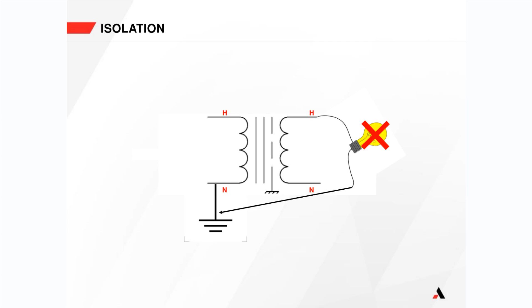And also, a transformer blocks DC. So if you don't know about the design of a transformer, DC cannot pass through a transformer. You've got to build up and then collapse the field. And that's what AC does. And then that gets magnetically induced to the secondary. If you just put DC into the primary of the transformer, then it will saturate the transformer, and it blocks that DC from getting through to the other side, to the secondary of the transformer. So in truth, if you had a fault within your rectifier bridge and the DC was allowed to short circuit to the secondary, it cannot get from the secondary to the primary and impose DC onto your MCC, onto your 480 volts. It's impossible. It also reduces ground loops because of the isolation from ground, and it also attenuates noise. So they're all the reasons why we use an isolation transformer. Okay.